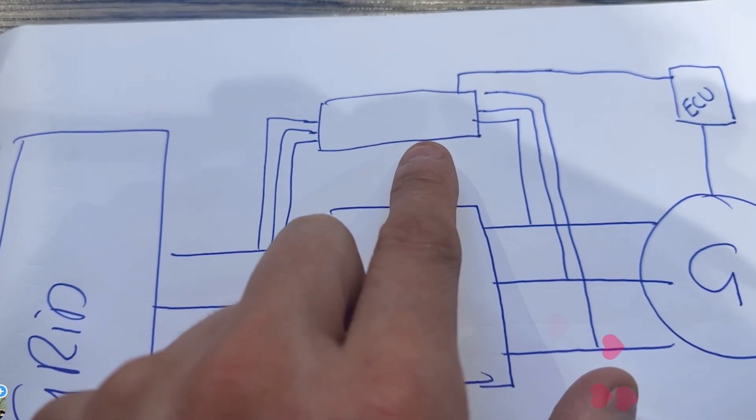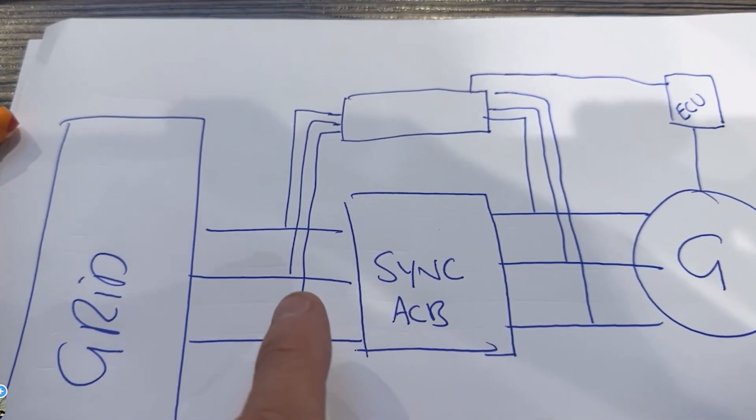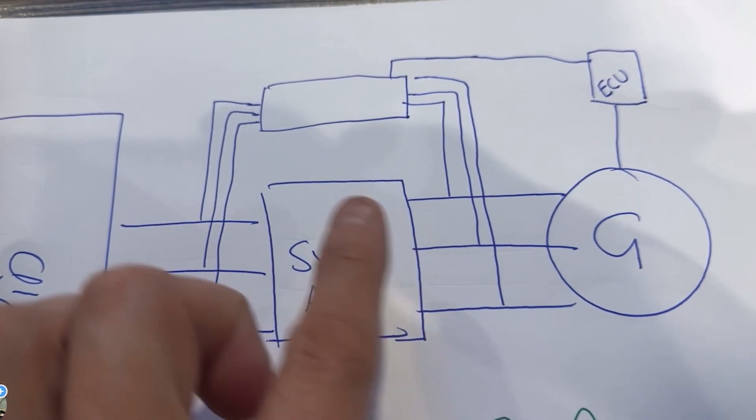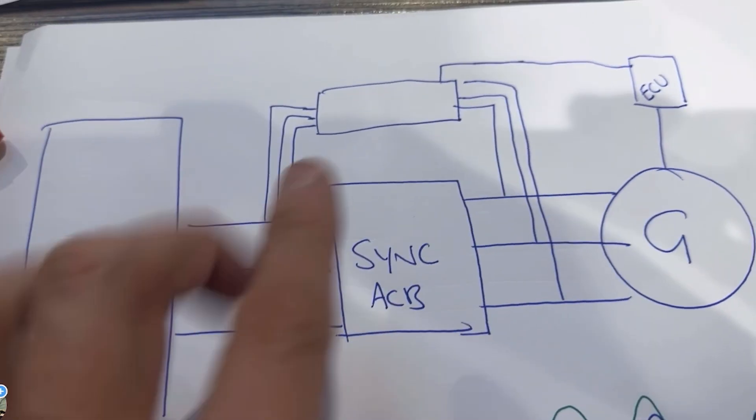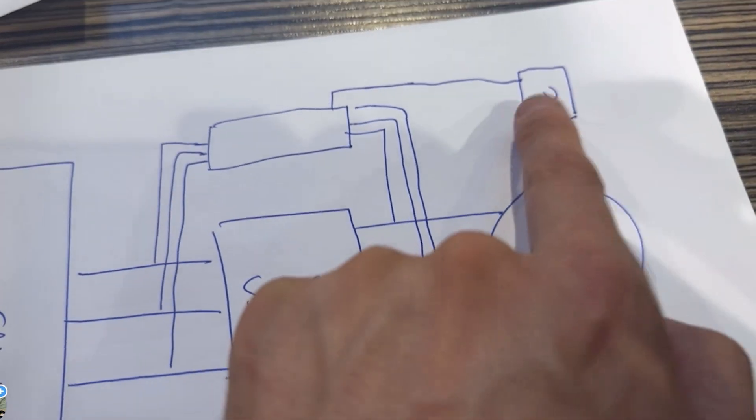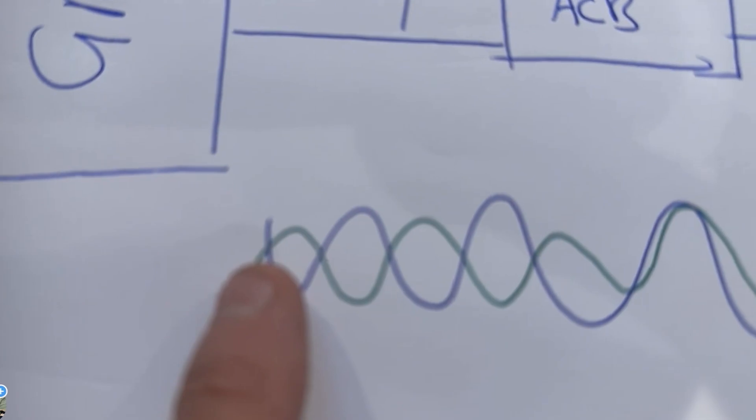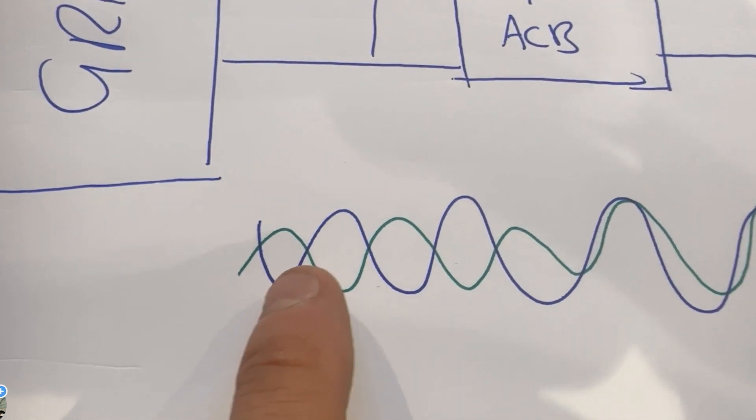With this ACB, let me draw that, the sync breaker needs to synchronize the generator to the grid, but the sync breaker is just a switch. So the synchronization controller is capable of measuring each side's voltage, current, all that bollocks. It makes sure it's going the right way, is it okay, yes it is.